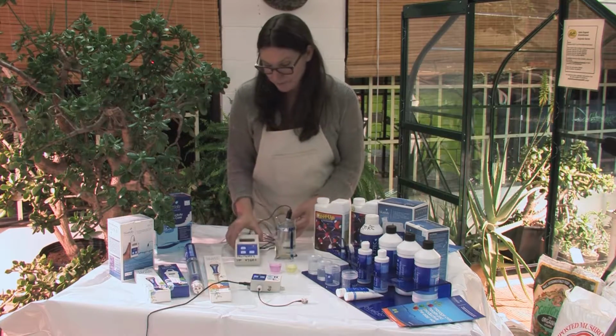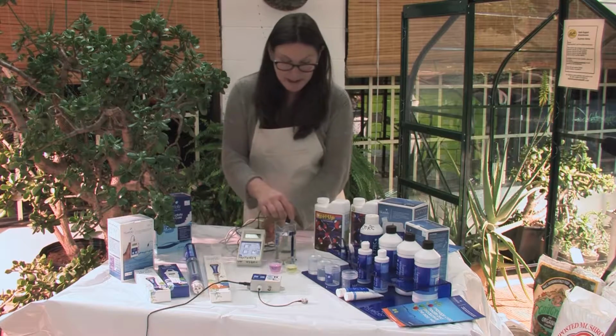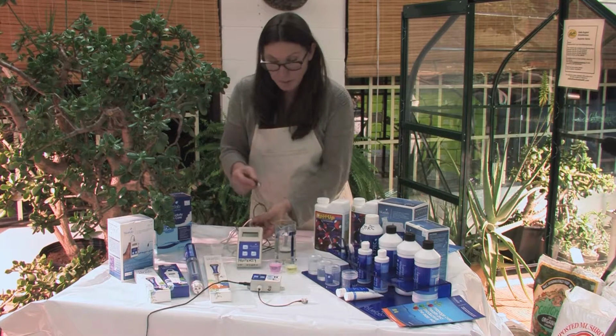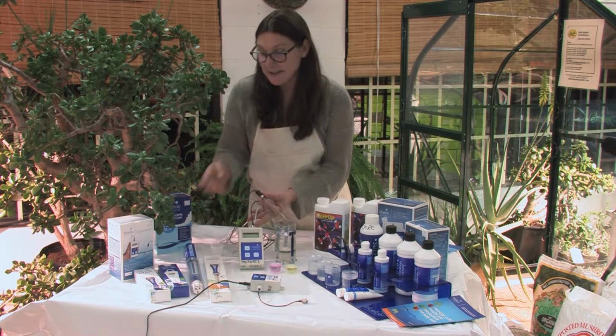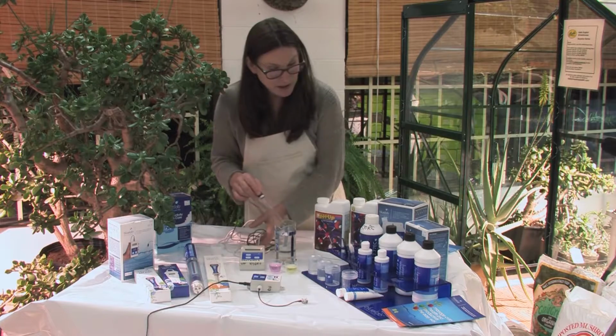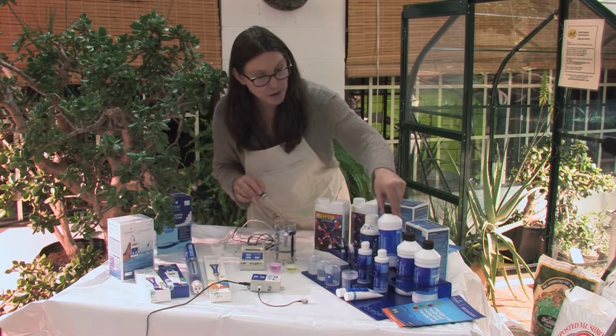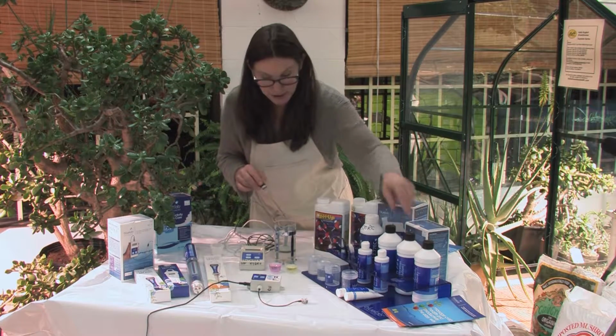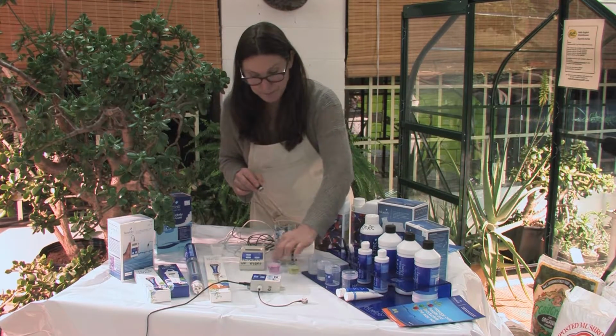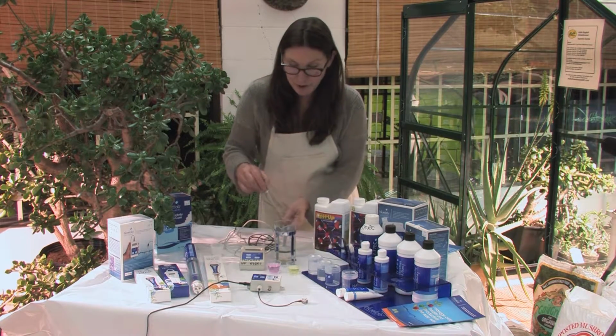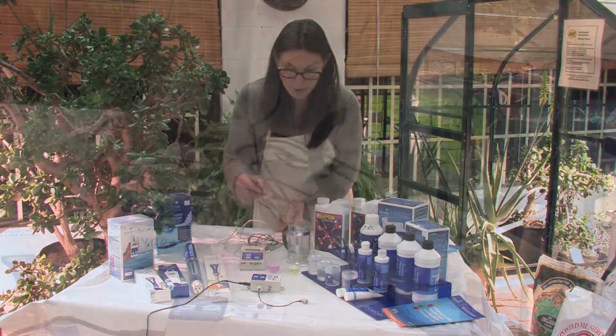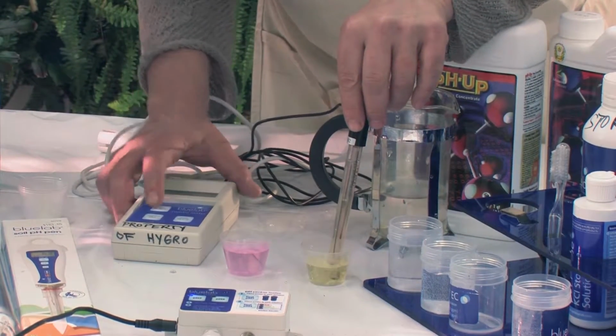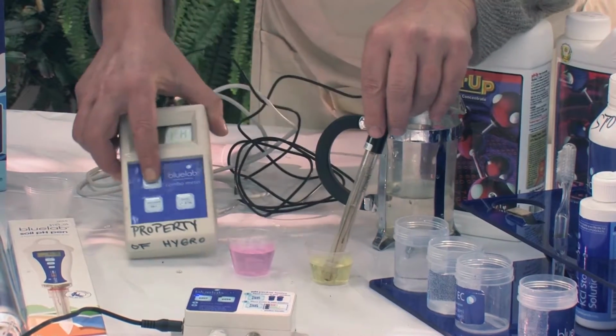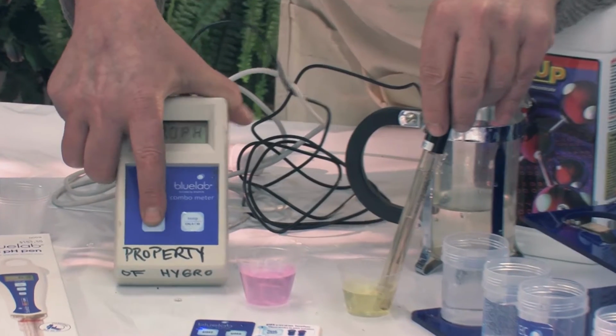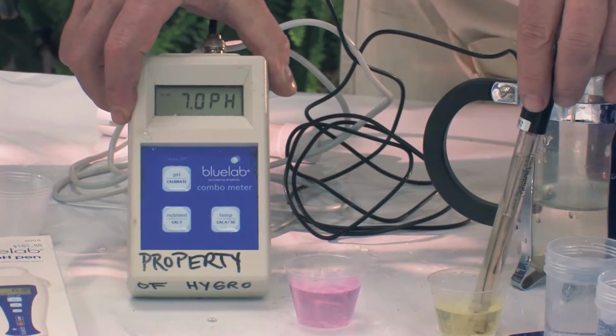I'll show you how to calibrate a pH probe. So this is our combo meter or Truncheon meter probe, but even if you're using a pen, you calibrate it in the same way. We've got our pH 4 and our pH 7 calibration solution. This is the 7, this is the 4. So we always start with the 7. We've got our clean probe that's been sitting in fresh tap water. Hit the button until it flashes, the pH calibrate button. And there it goes. Then we push 7 and it's calibrated to 7.